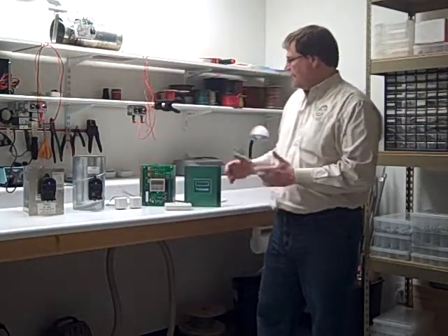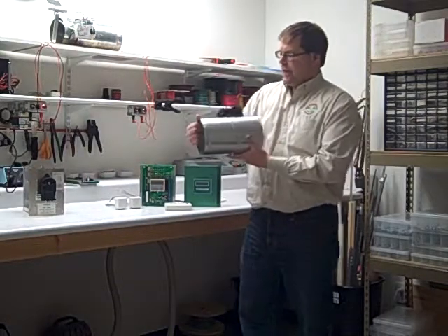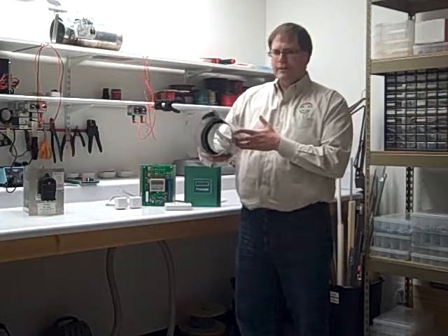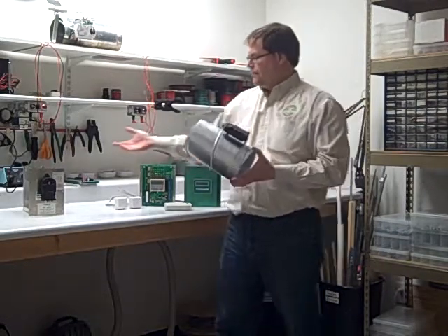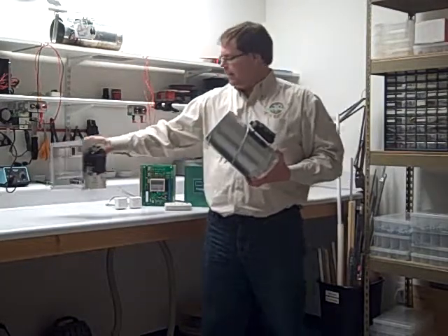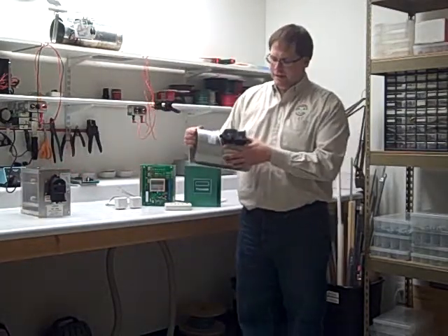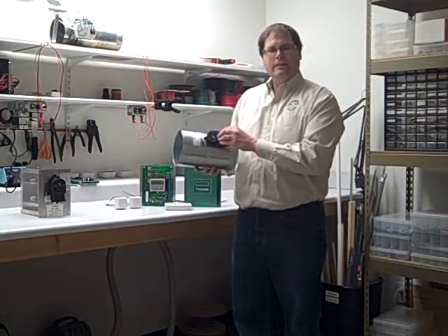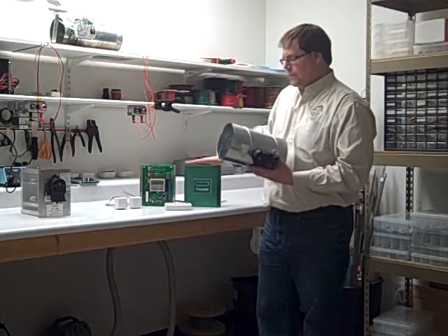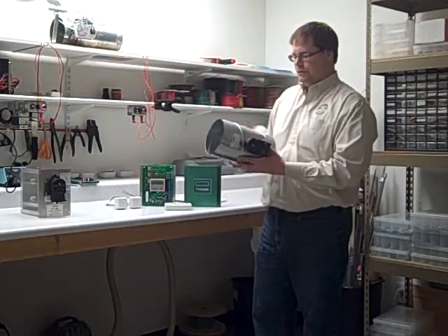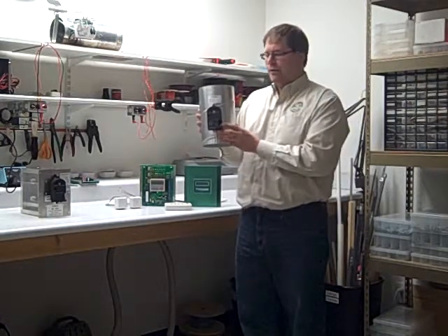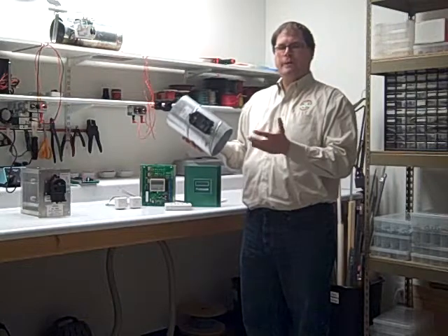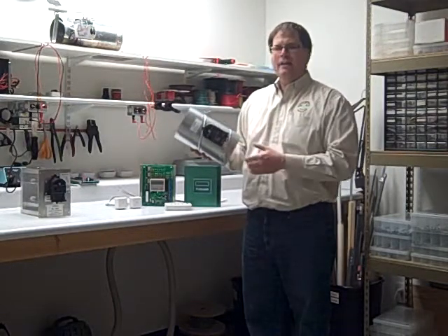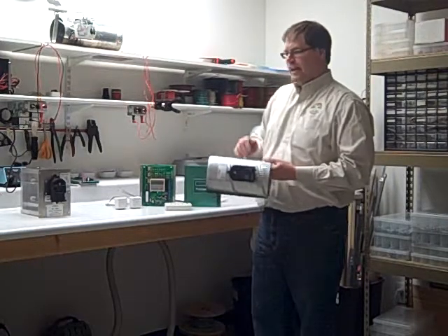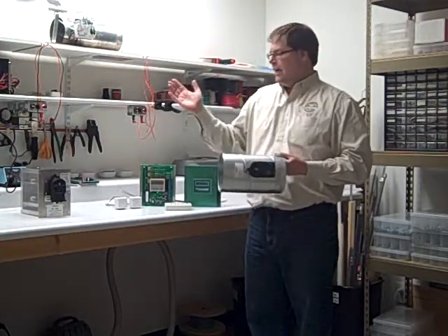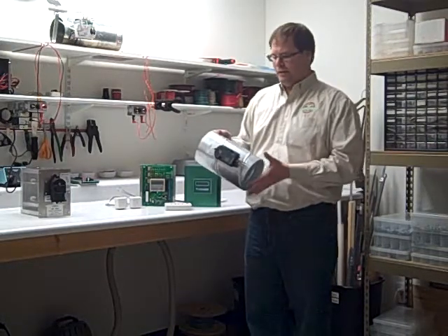And then as far as the dampers go, pretty much our standard dampers that you're used to with the 5-year warranty, heavy-duty construction, spiral pipe on the round, real heavy-duty rectangular dampers as well, but you'll notice on the actuators it is a different style actuator. These are wirelessly controlled. In other words, the signal coming from the panel is wirelessly transmitted to each of the dampers. You do need to get 24 volts to power the actuators, but you can get that 24 volts from anywhere, which we believe is a much simpler task than having to run wires all the way back from the panel to the damper. You can just mount a transformer up in the attic or in a crawl space and power a large number of dampers, even from a 40 VA transformer.